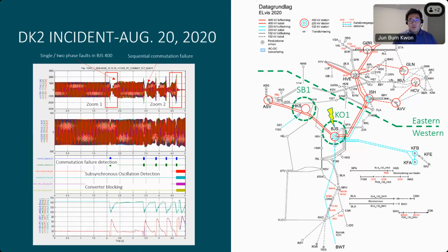The main reason was that the vendor-specific model was not able to capture such multiple sequential events precisely, and some of the modeling details of the protection and trip sequence in the RMS dynamic models were not good enough to represent such event cases.